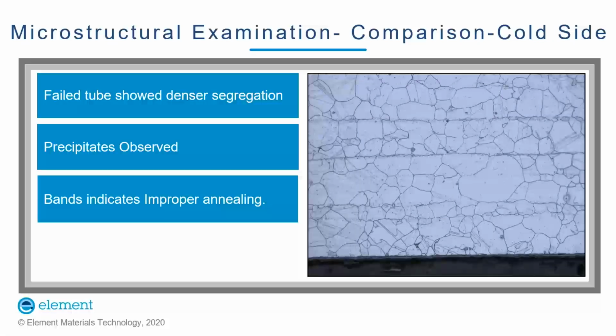Microstructure analysis was also conducted on the non-failed tube in order to understand the issues with the failed tube. It was necessary to understand why only one tube failed among the bunch of tubes in the heat exchanger. A comparison between the failed and non-failed tube was done for both the cold side and the hot side, and it's presented in the following slide.